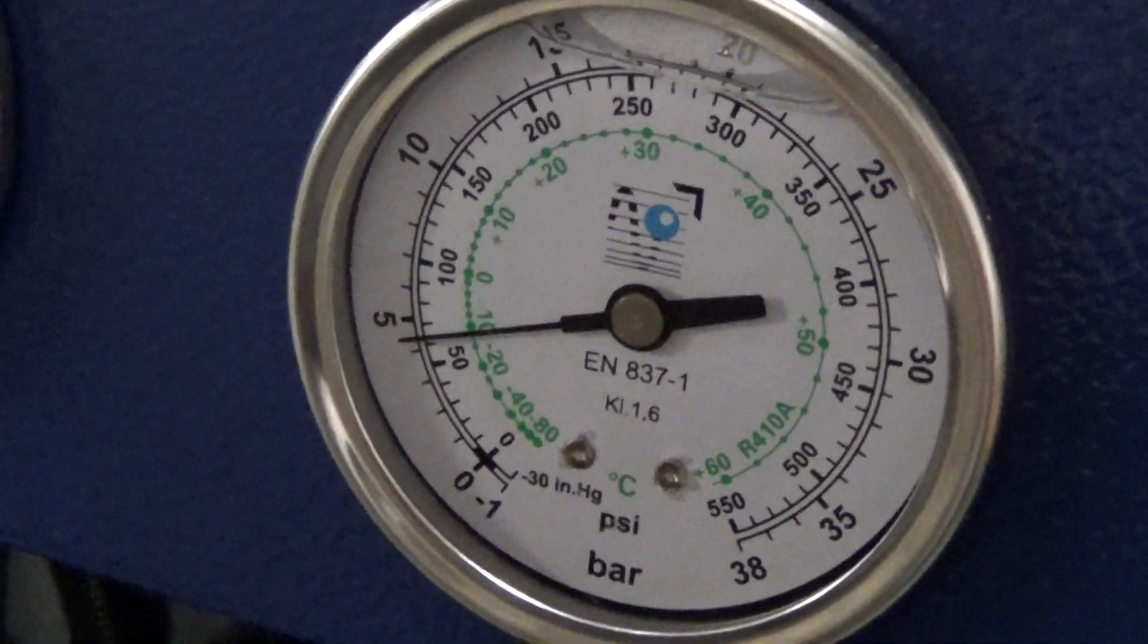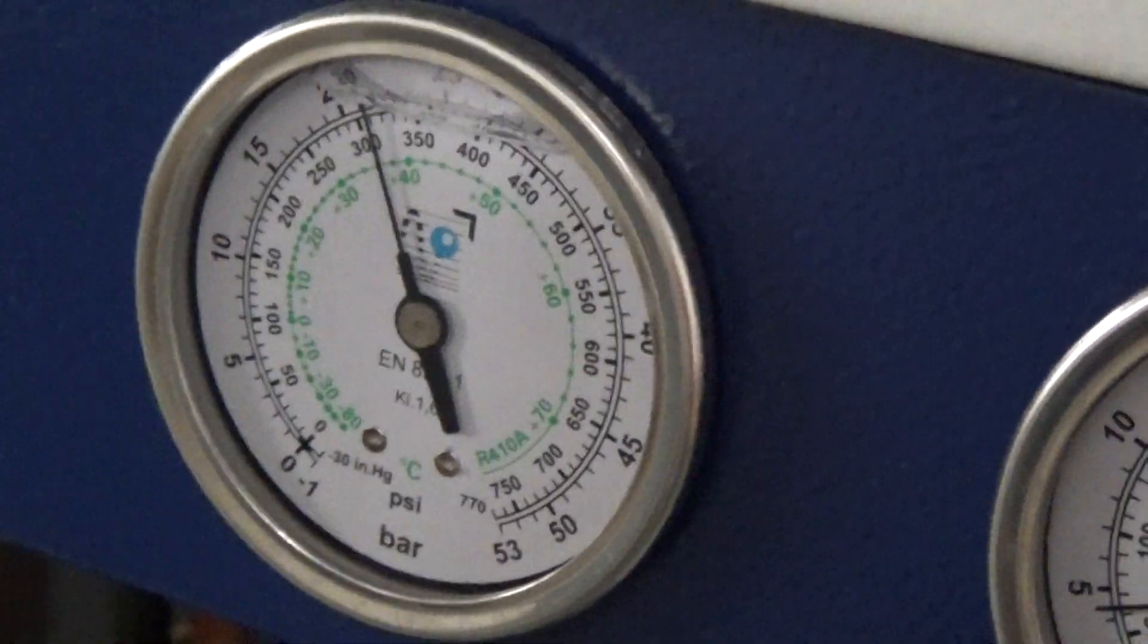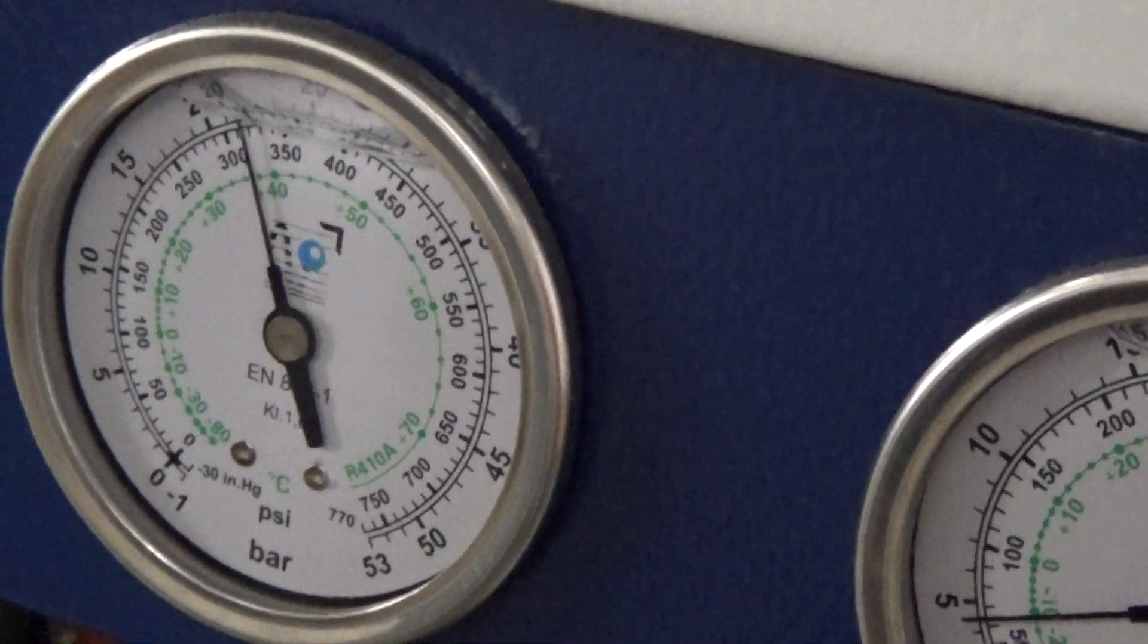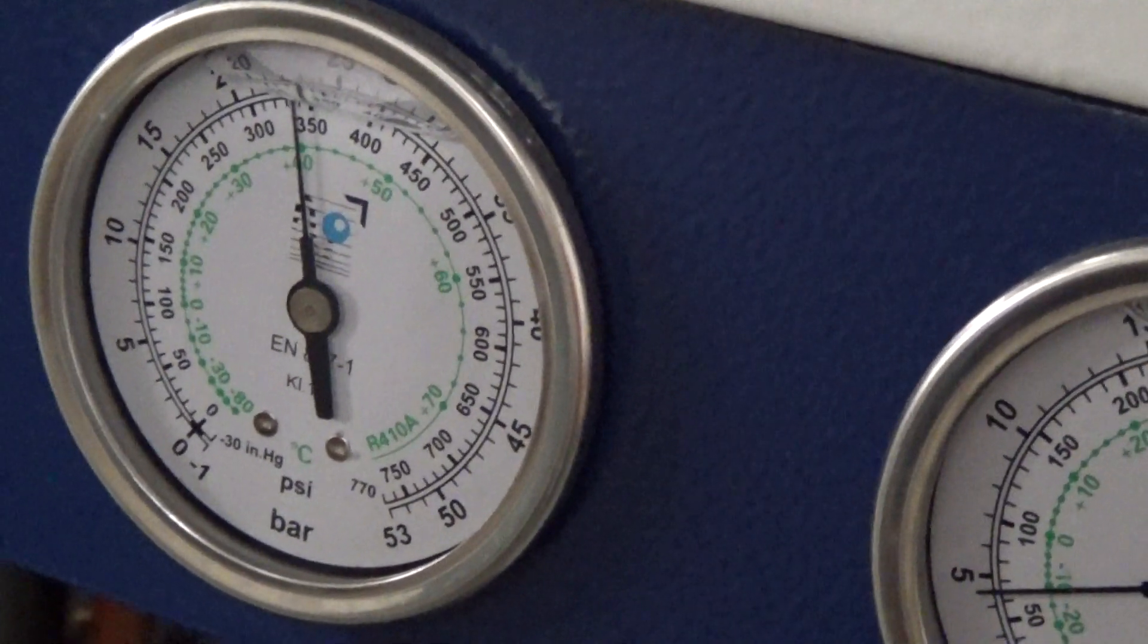You can see the fan just turned up. When the fan turns on, you'll see that the pressure drops a little bit. That's the high pressure gauge on the left.